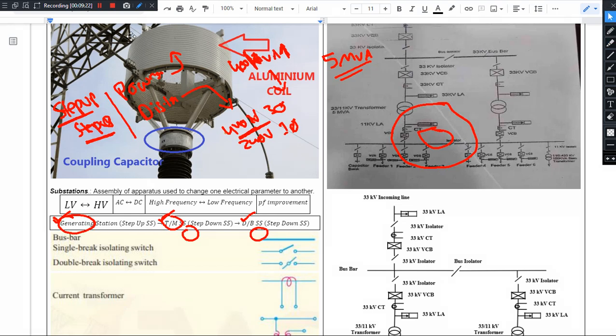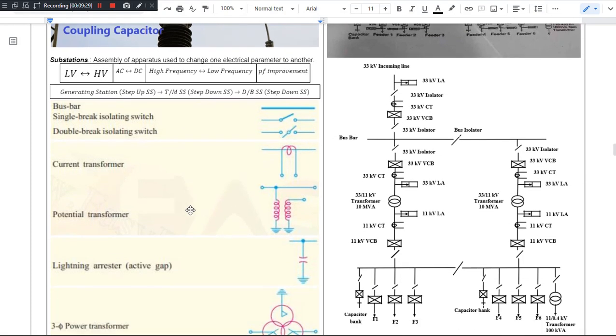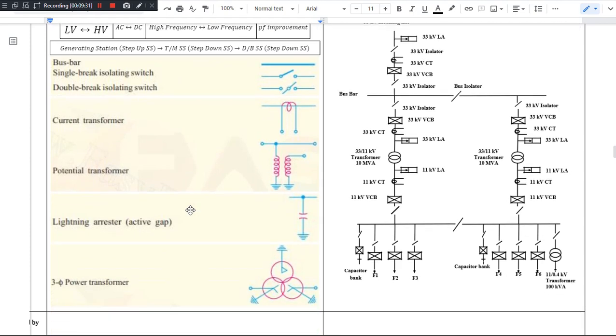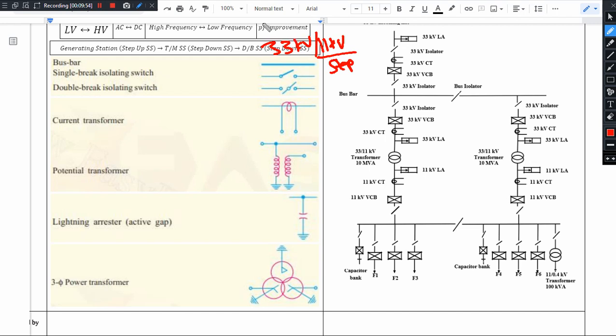We have a generating substation, transmission substation, and distribution substation. In Telangana, we have 33 kV and 11 kV voltage levels — a 33 by 11 kV step-down substation is common. There are also 66 by 11 kV substations, which are more economical because higher voltage means lower line losses. However, 33 kV has been used traditionally since the beginning, so it continues.